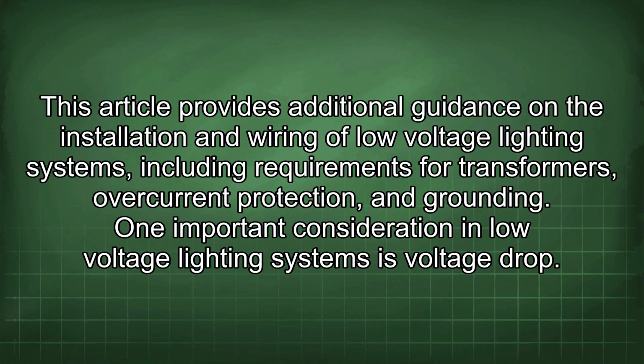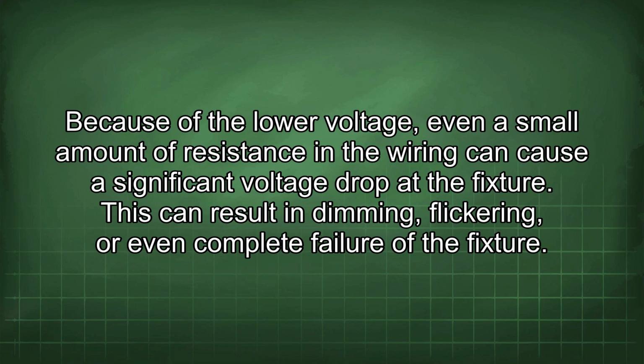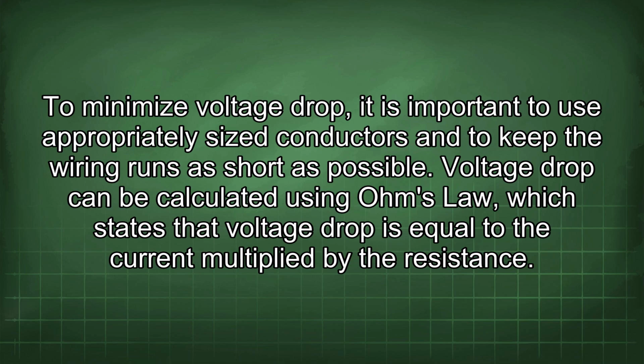and grounding. One important consideration in low-voltage lighting systems is voltage drop. Because of the lower voltage, even a small amount of resistance in the wiring can cause a significant voltage drop at the fixture. This can result in dimming, flickering, or even complete failure of the fixture.